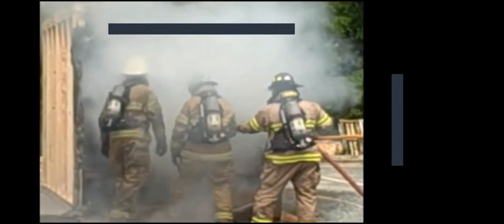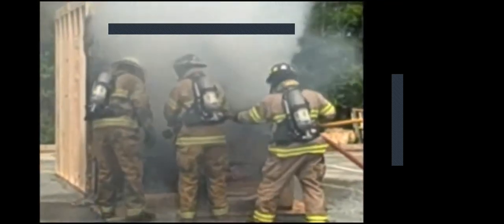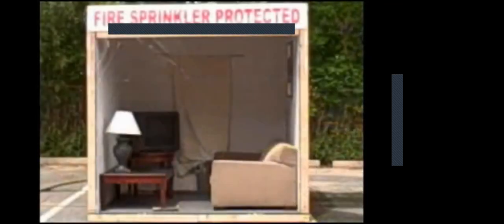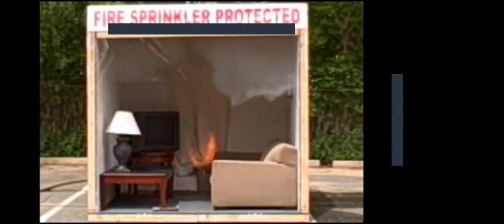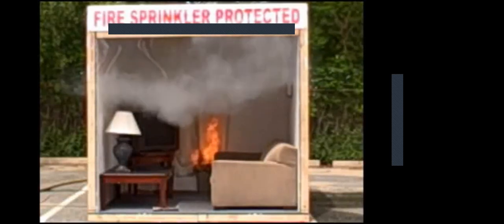Okay, and here again, we go. No accelerants of any kind were used. That was just paper, tube, and fabric. Same scenario with a sprinkler. Now here again, you should hear the smoke alarm go off first. 15 to 20 seconds. There's the smoke alarm.